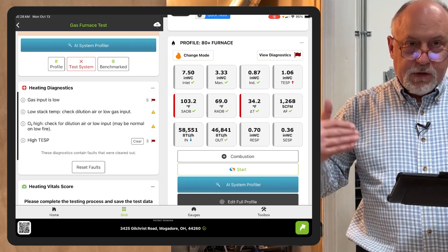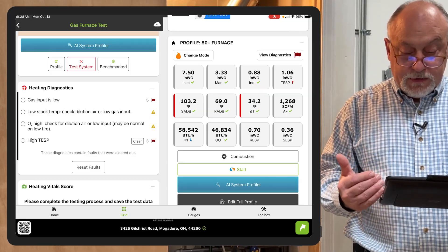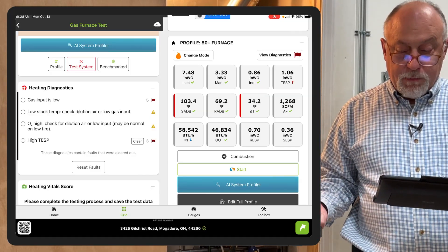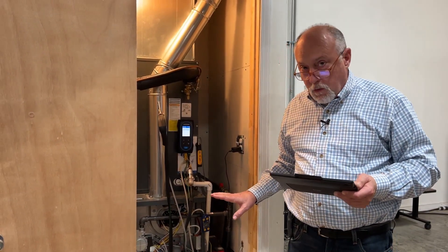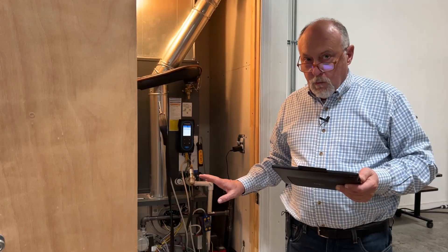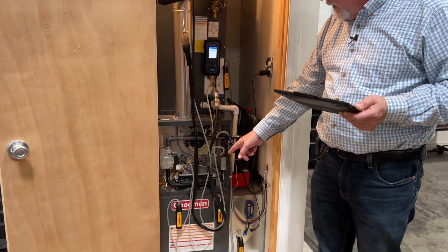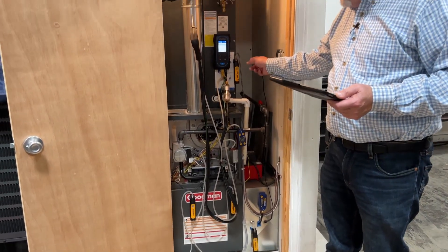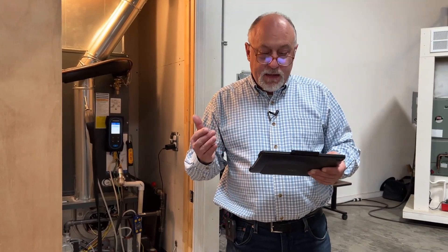So it makes it a lot better. If you're standing there with customers behind you and you're not doing a combustion analysis because you don't own one yet, you're only seeing on the screen the inlet pressure, the manifold pressure, the induced draft pressure, and static pressures. This is where we highly recommend that you get multiple manometers. I have five manometers on here — measuring the incoming gas pressure, manifold pressure, return static, supply static, and induced draft pressure.